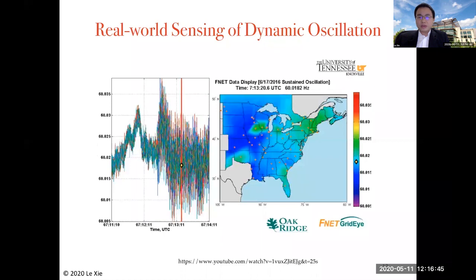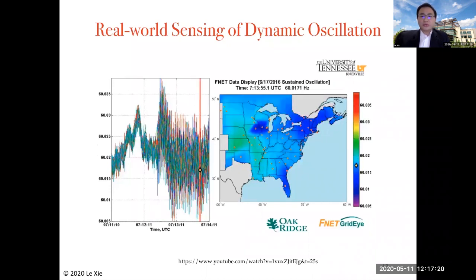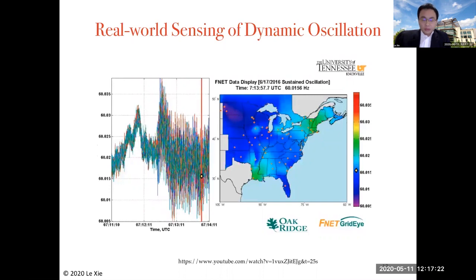But if you ask a very experienced power engineer what's going on, he or she might say it looks like there's some kind of small oscillation going on, but not a big deal, because if you look at the frequency measurement, the floating bar, it was actually in a very tight band, something between 60.015 and 60.025. So all is good, it's just a small perturbation, like turning your lights on and off. Not a big deal. So they may say, okay, it's good I can see what's going on, but what's next?